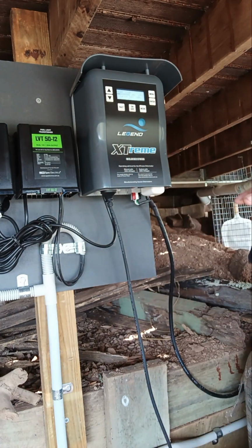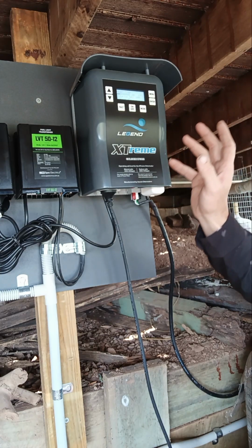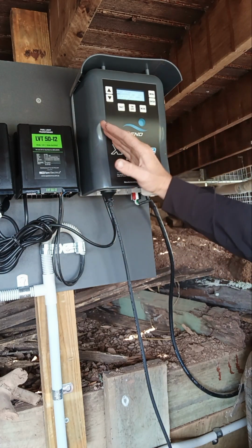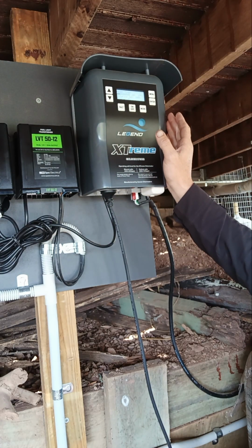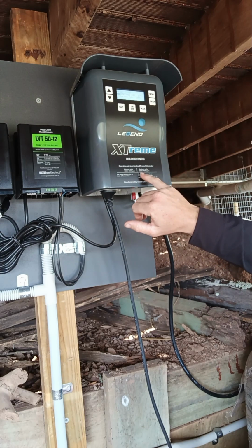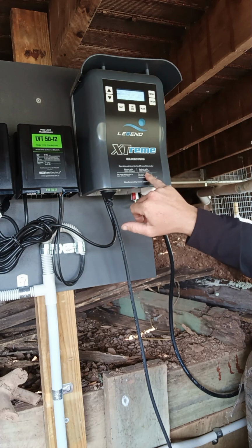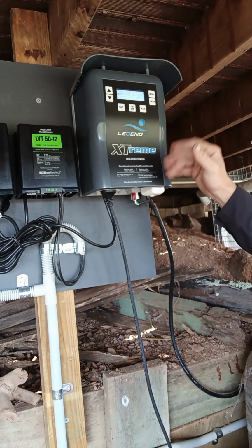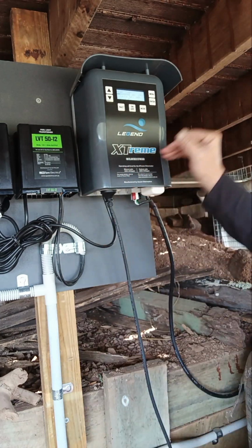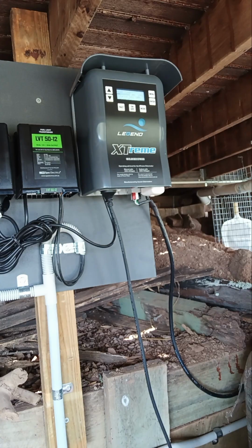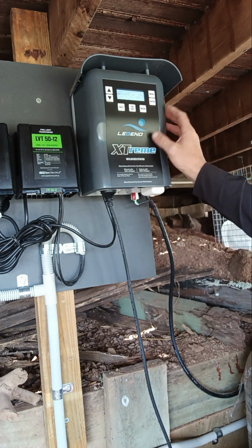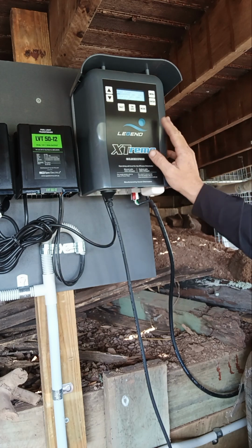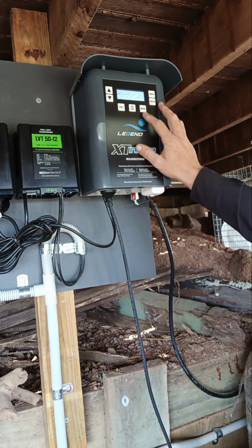So we'll count the bags, and that way from 0 to where you're at, we know it takes about 16 bags. You want to stay in the parameters of 3,500 to 7,000 parts per million. It's fine to go a little bit over, but you don't want to be in the 10,000 or 12,000 range. A little bit over is fine, but you don't want to go too much. Otherwise, that's pretty set and forget for the use of this unit.